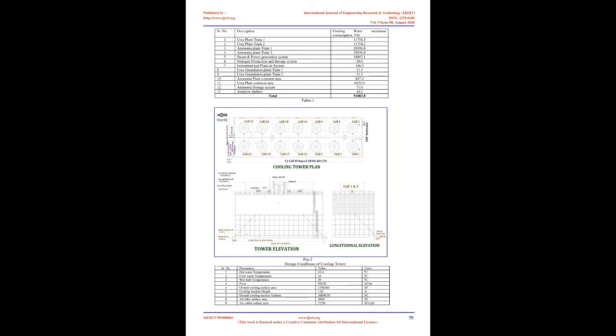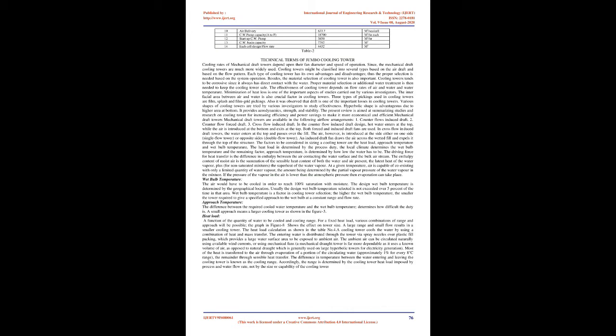4. In order to prevent corrosion, scaling and growth of organic matter in the cooling water circuit, a dedicated system of chemical conditioning has been provided. In principle, cooling water conditioning is obtained by the following dosing systems: chlorine dioxide, 14pK01, corrosion inhibitor phosphate base, 14pK02, antiscalant, 14pK03, corrosion inhibitor zinc base, 14pK05, and secondary biocide, 14pK06.